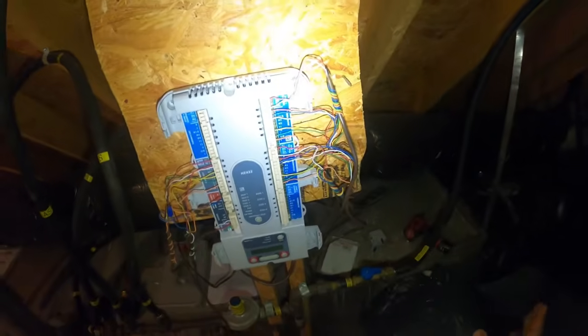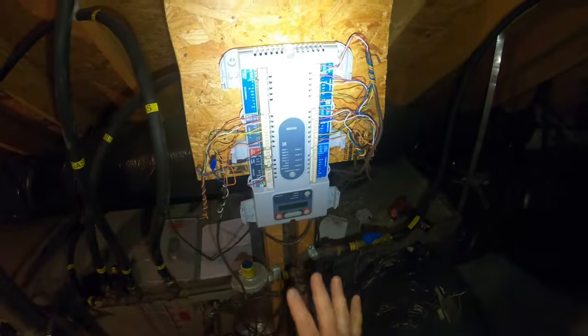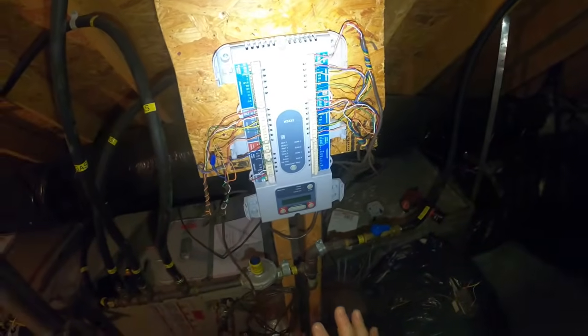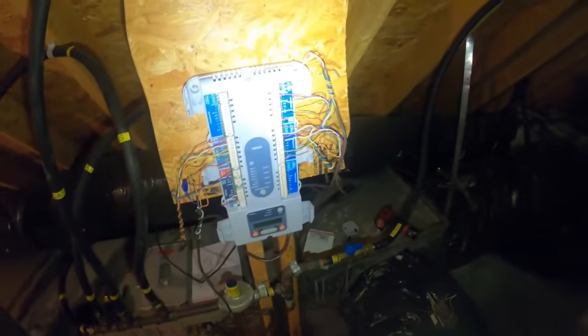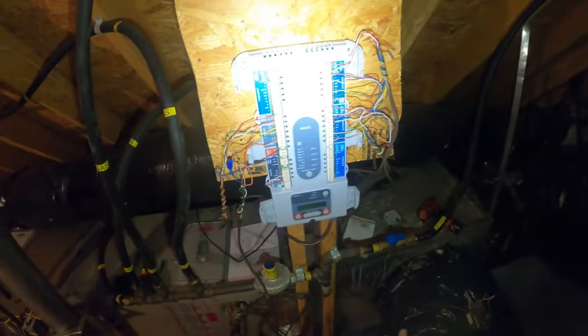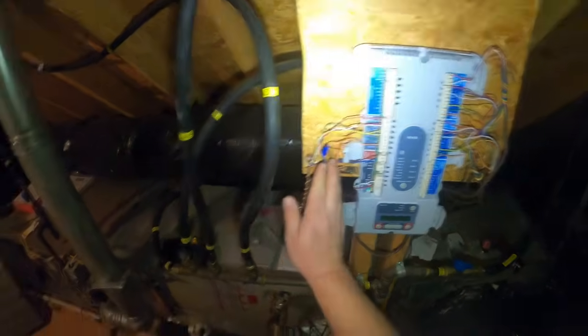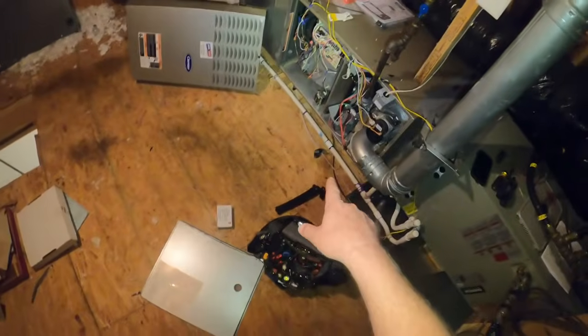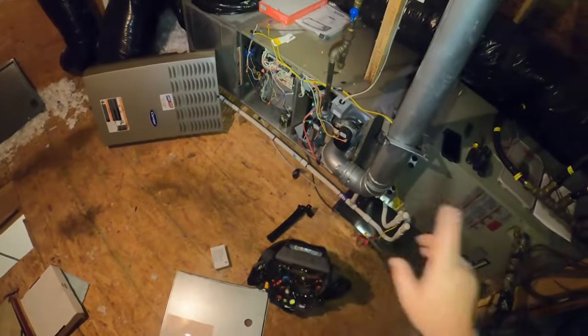And we're going to use the outdoor temperature sensor to control my lockouts. More than likely, I'm just going to set a lockout in this thing that above 40 degrees, we're running the heat pump. Below 40 degrees, we're going to run the gas, and just leave it at that. It's the simplest way to do it. Did have to go over here and add a secondary transformer because they also did not do that.